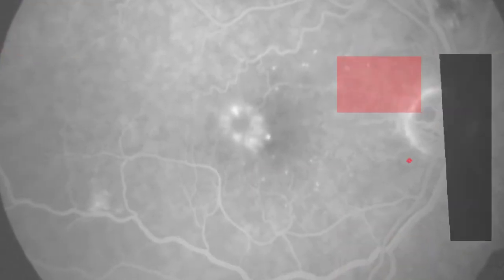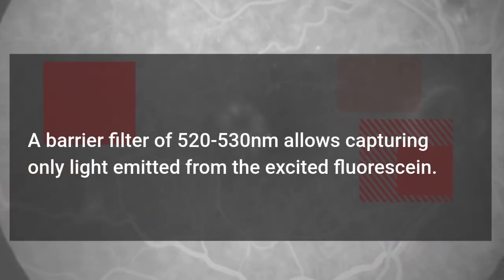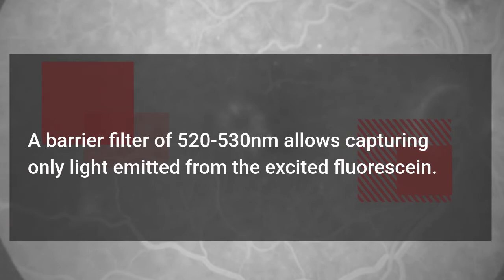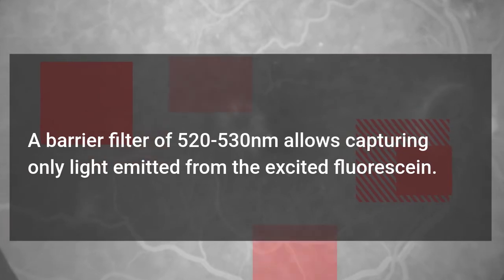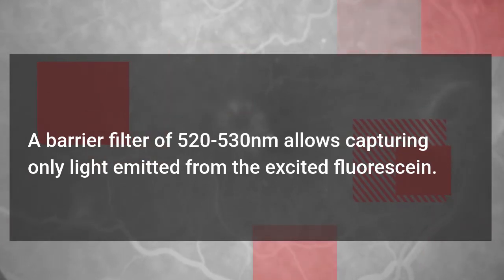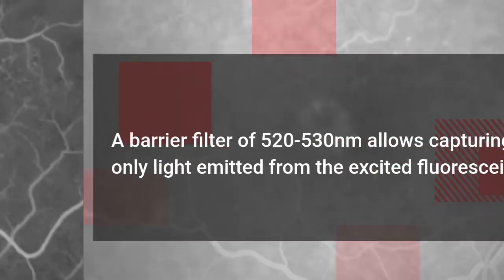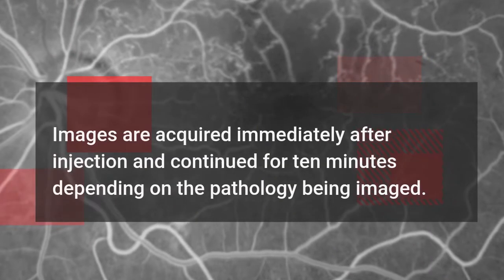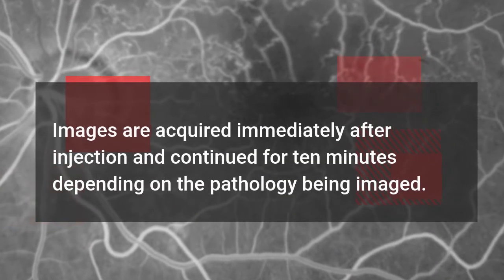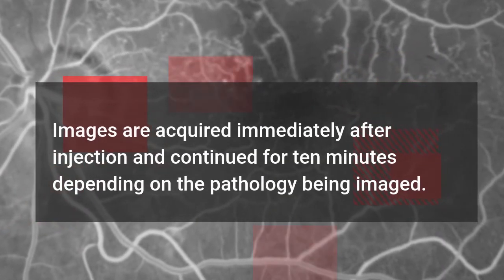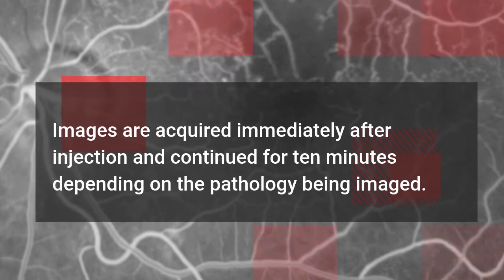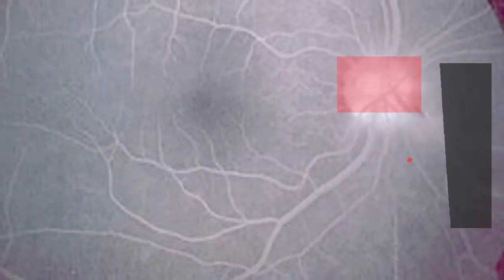A barrier filter of 520 to 530 nanometers allows capturing only light emitted from the excited fluorescein. Images are acquired immediately after injection and continued for 10 minutes depending on the pathology being imaged. The images are recorded digitally or on 35 mm film.